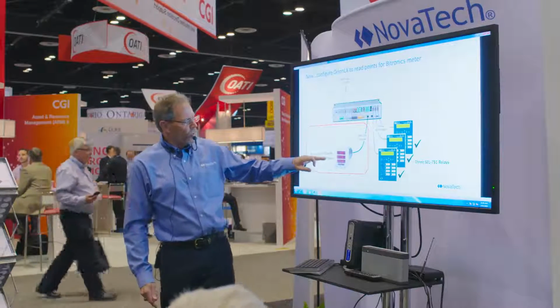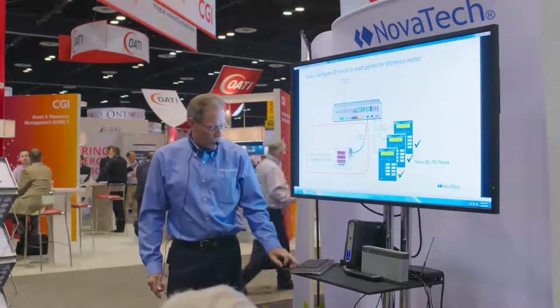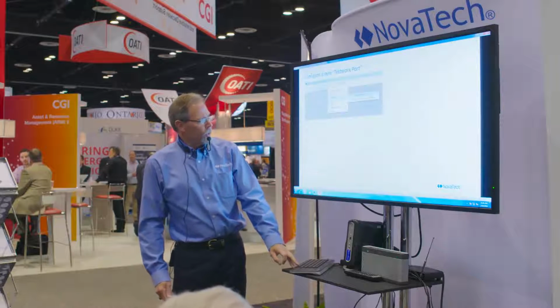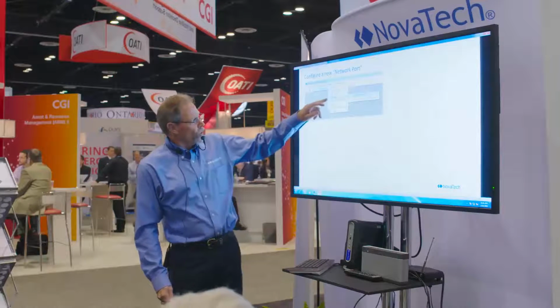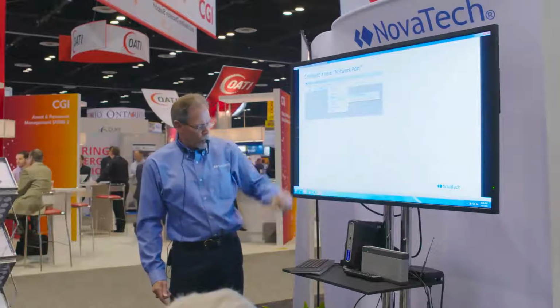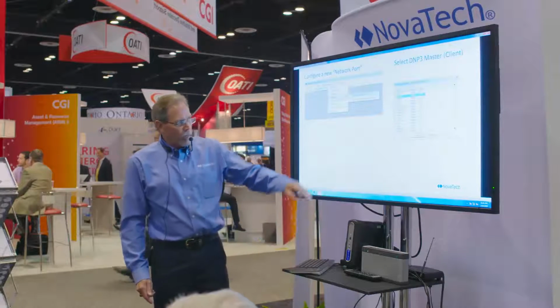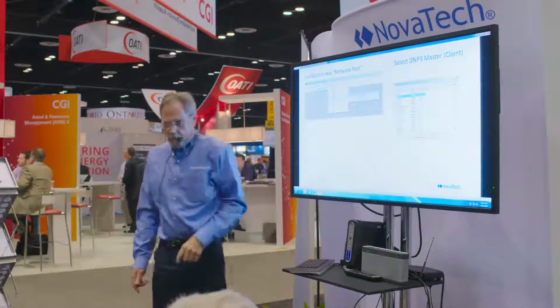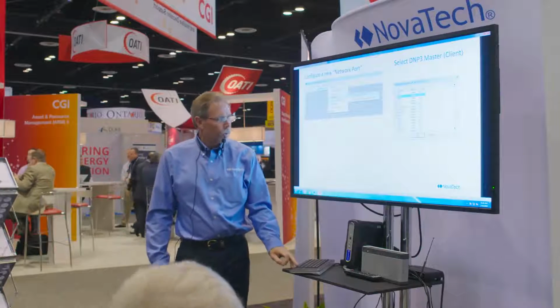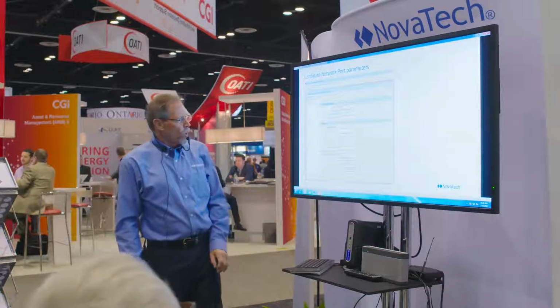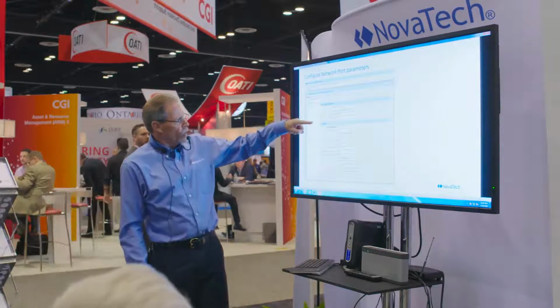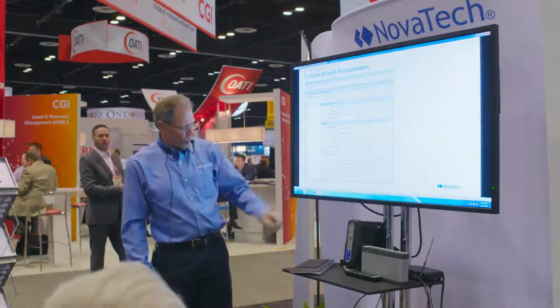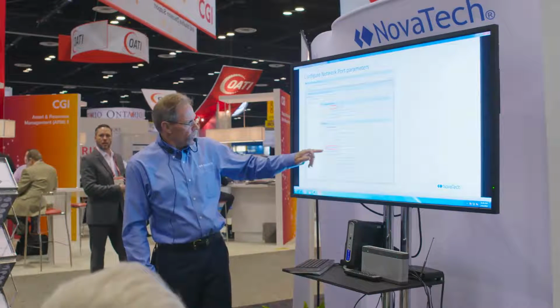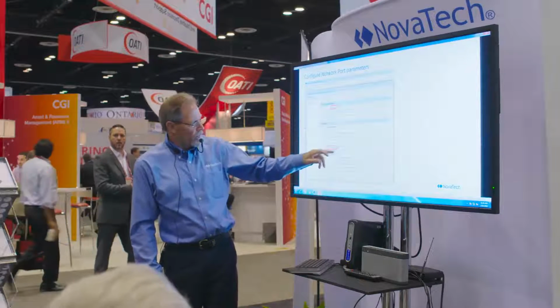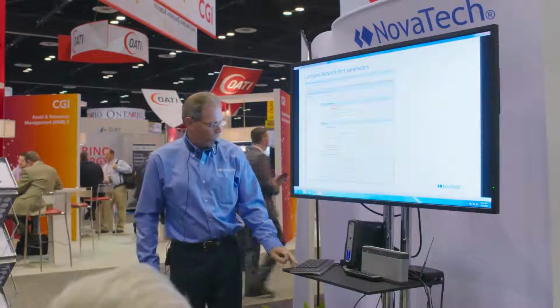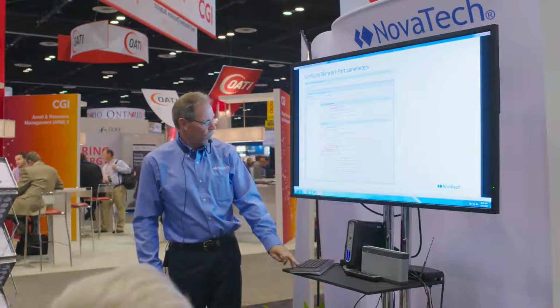Now on the Bitronics, it's going to be a network connection. So instead of the serial drop-down menu, I'm going to go to the configure network port. And from here, I'm going to select DNP3 master. Now when I select DNP3 master, the first thing I'm going to do is go in and set up a specific port name and the IP address that we programmed into that Bitronics M650 meter.